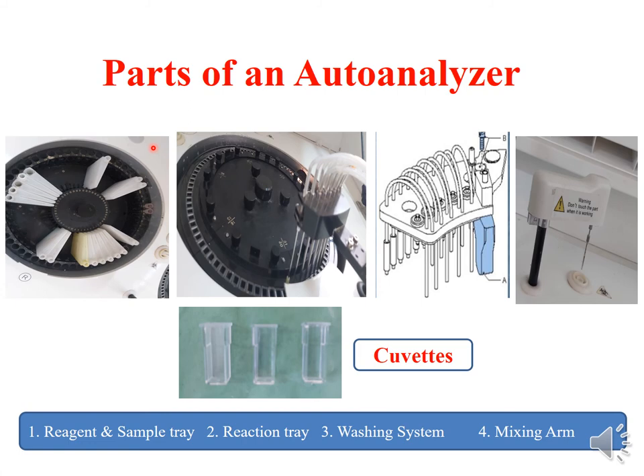The reagent arm will dispense reagent into the cuvette and the sample arm will dispense sample into the cuvette, and the reaction will occur. This is the washing station — the schematic diagram of the washing system or laundry system, which will wash all the cuvettes whenever testing is over.